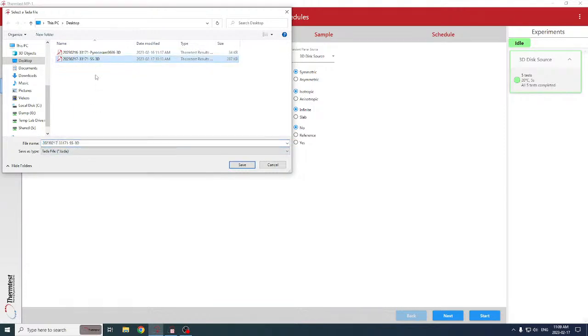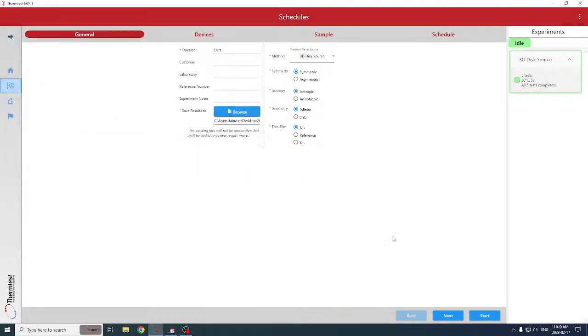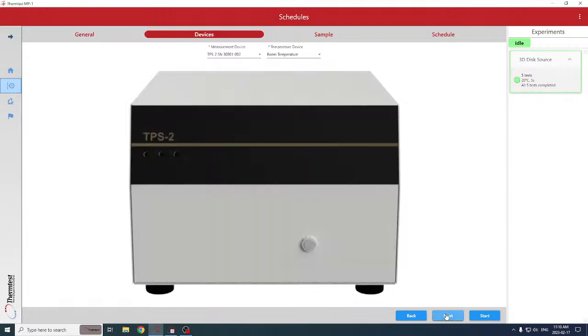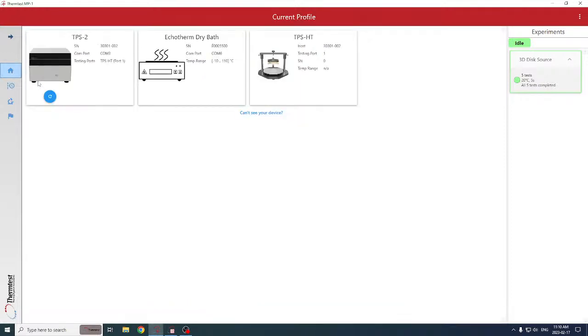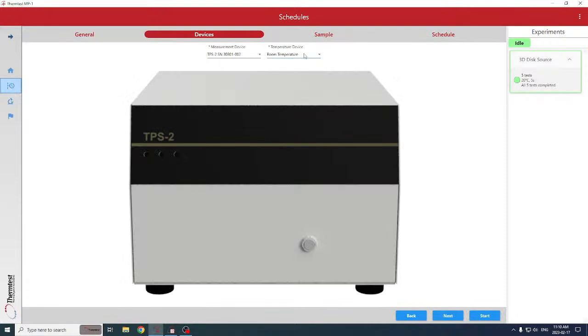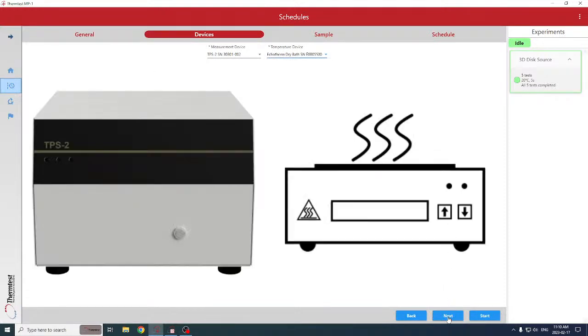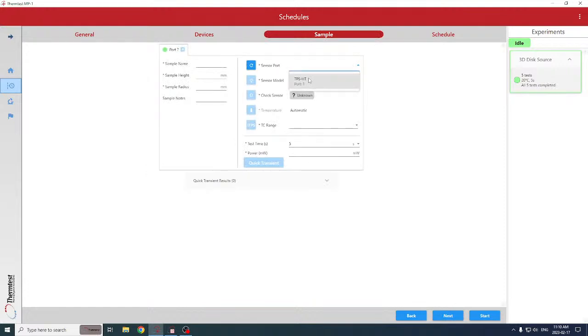So here's a previous experiment. I could append this, or I could just add another location for the new data. So we're going to do symmetric, isotropic, semi-infinite body, and not thin film. The software auto-detects what is plugged into it. If you want to review that, you can always go to the home, and it shows you that right now the controller is detected, the dry bath is connected, and the high-temperature sample holder that's sitting on top of it is connected. So we're going to select the dry bath as the temperature option. And the port we're going to use is one. Again, on the TPS-2, we only have one port. On the MP1, which is our multi-port device, we have four ports.